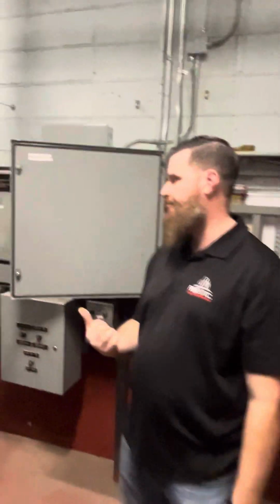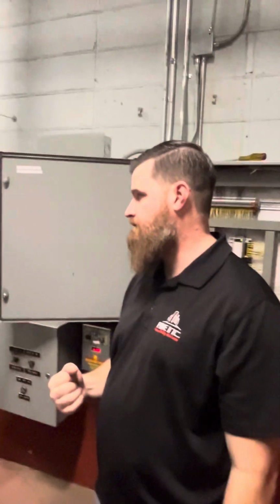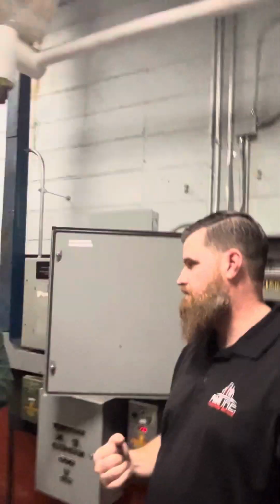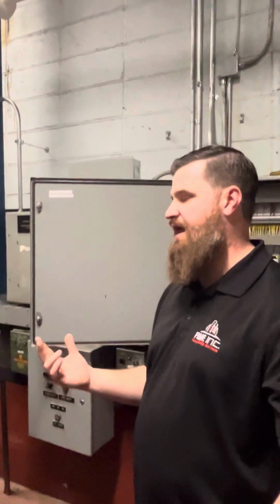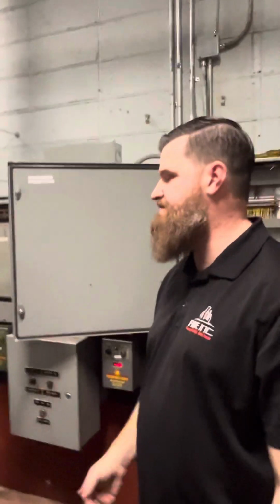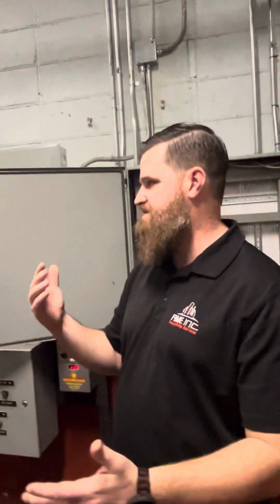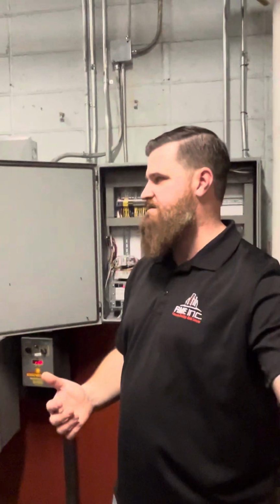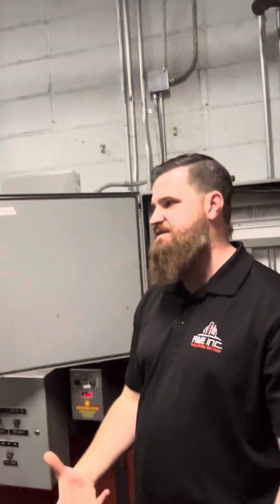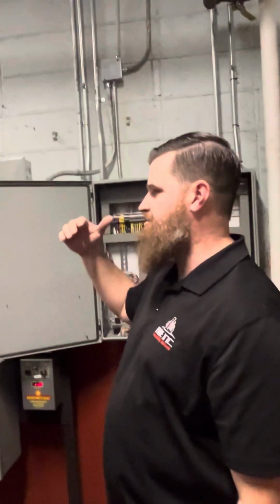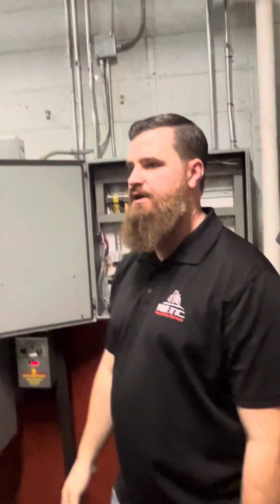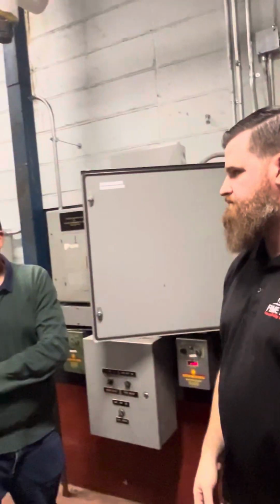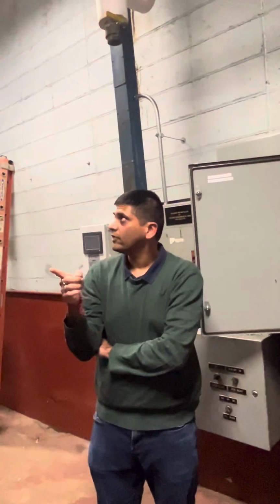How do you decide that it has to be 4 psi? It's just a generic set point. I've seen buildings run on a straight 3 psi constantly. I've seen some buildings do an outside air reset on the pressure, so maybe we run 2 pounds when it's 55-60 degrees outside, and 5 or 6 pounds when it drops to 30 degrees. But you guys can correct me if I'm wrong.